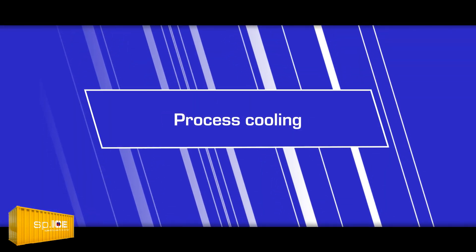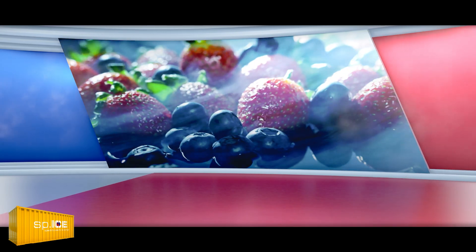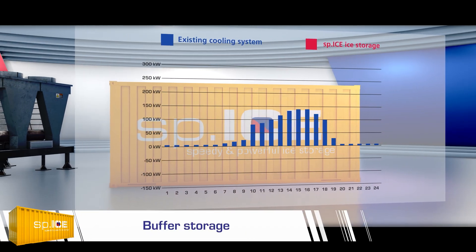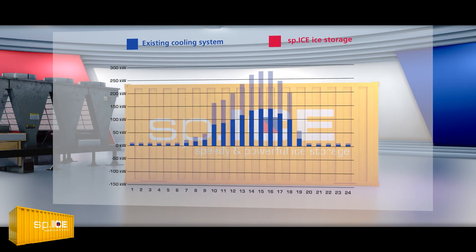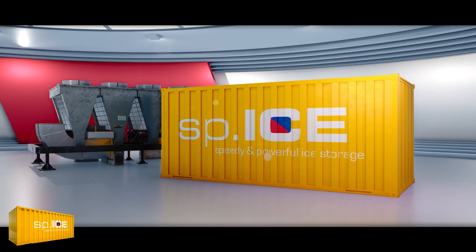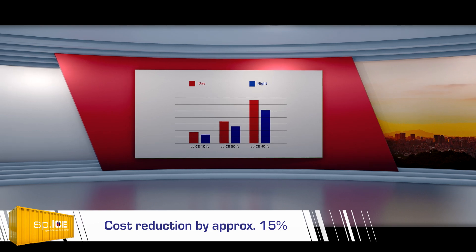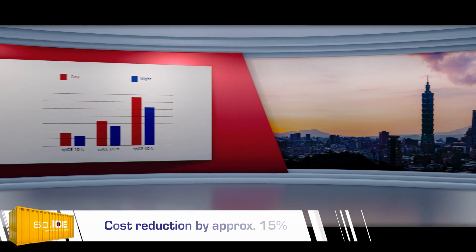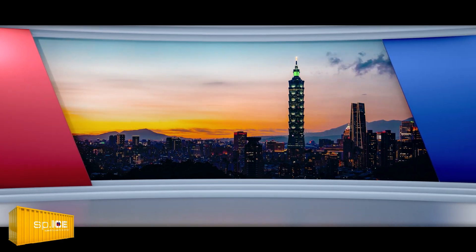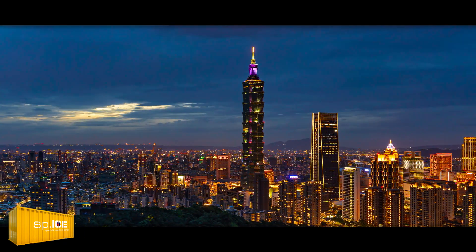Process cooling. Do you need a flexible solution for the process cooling that is required in your production? In this instance the sp.ICE system takes on the role of a buffer storage. In a few nighttime hours, the entire cooling demand for the next day can be produced in advance and stored in readiness. The potential savings are all the more noticeable when there are greater differences between daytime and nighttime electricity tariffs. The ice energy storage is loaded using economical nighttime electricity and makes the required cooling available during daytime.